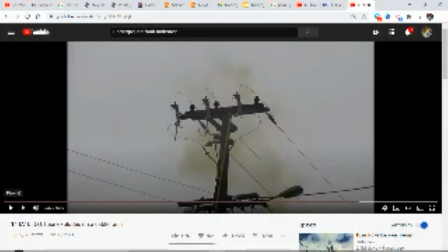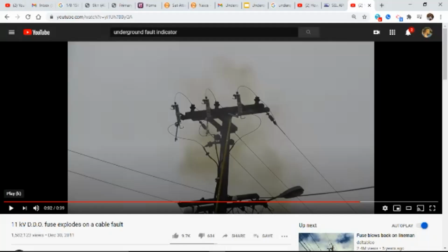Pretty decent explosion, you know, and everything on an underground dip. And I had an engineer tell me, and there are some different things going on as far as breaker settings. We'll talk about that later. That overhead faults or overhead problems, something that might be on the line, are typically 75% of the time temporary. What do I mean by that?